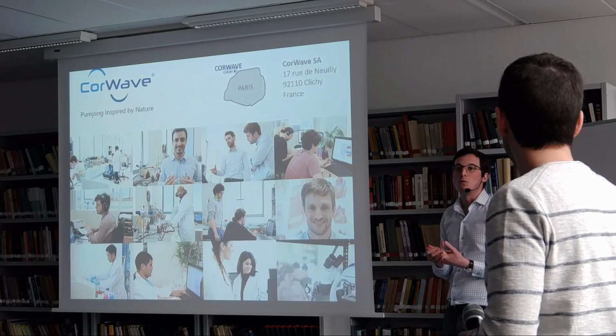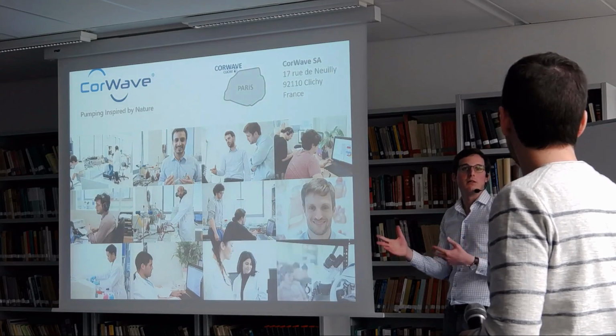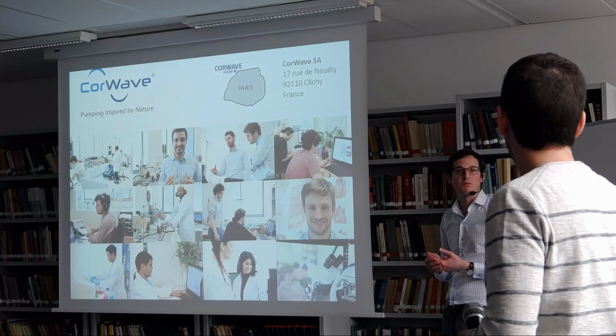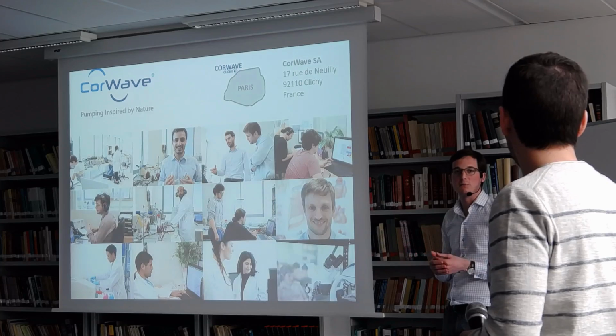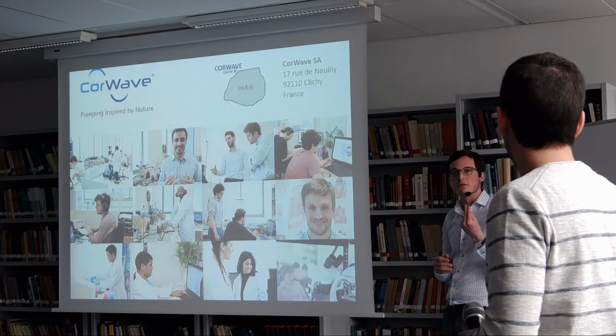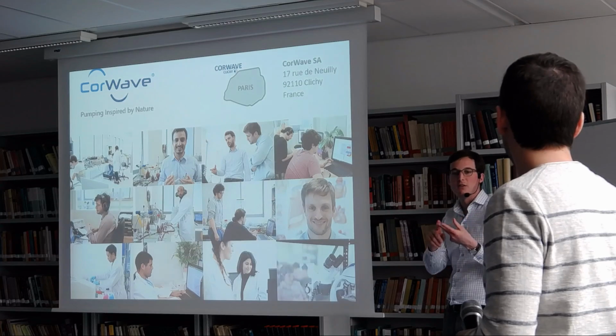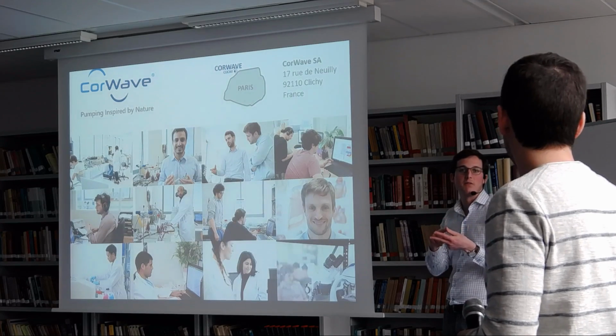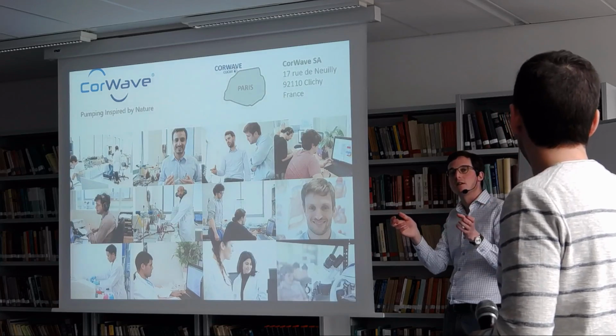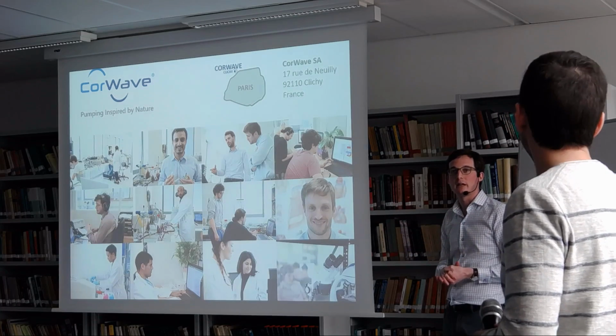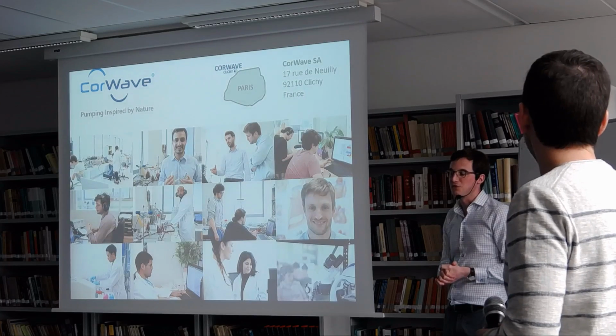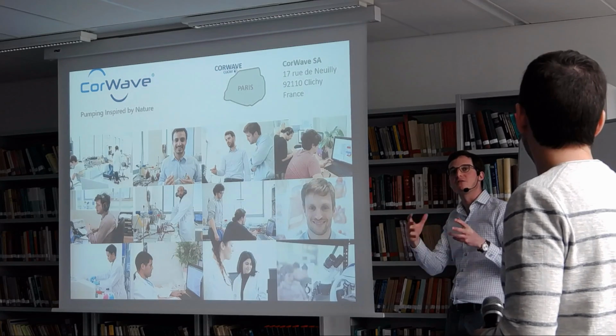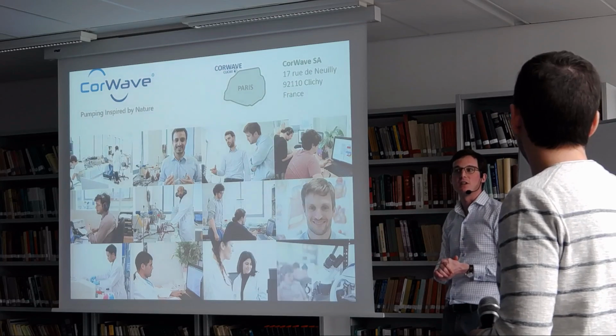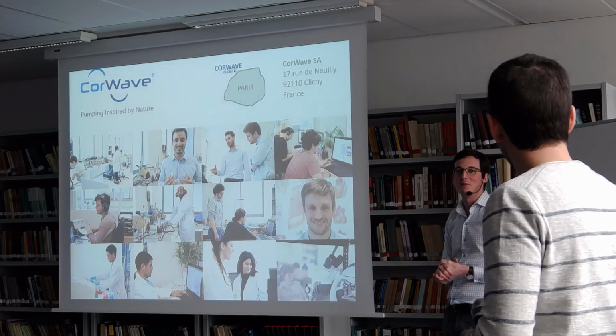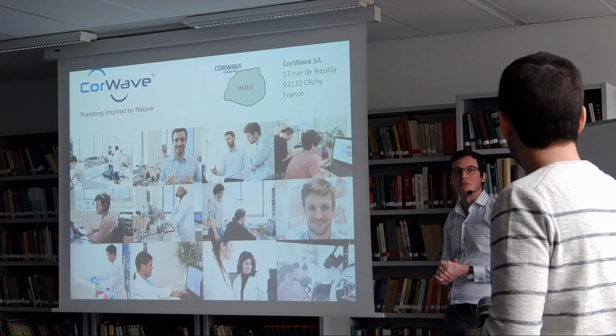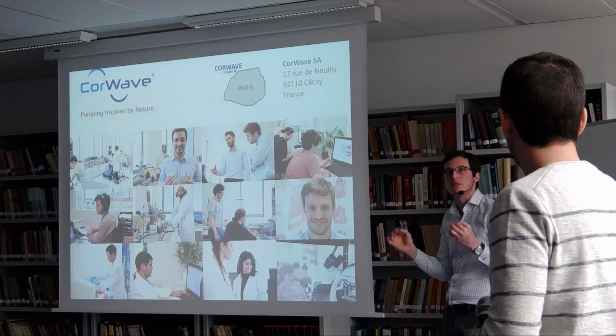And what we don't know yet is that there might be some stainless steel on the inside, just for parts which we can't make out of titanium, but this stainless steel is also biocompatible. So there are only 3 materials which will actually be in contact with blood: biocompatible stainless steel, titanium, and the biocompatible silicone. And everything else has to be encapsulated and hermetically sealed, which presents a whole range of challenges from a manufacturing and process point of view. Afterwards, you have to prove that it's hermetically sealed. You do helium leak tests. It's quite involved because you have to prove that nothing can penetrate to the inside.